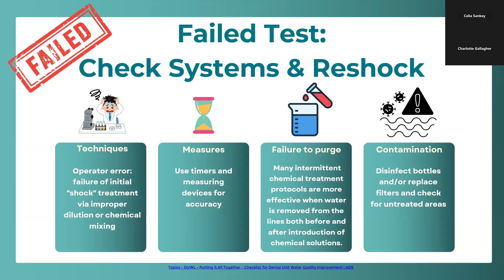After the shock tests are deemed successful, the water quality will then need to be maintained. This is our third step. Physical maintenance requires that all lines be emptied or purged during any vacations, nights, or weekends. Hit the purge buttons at the end of the day or just drain the lines to prevent stagnation.